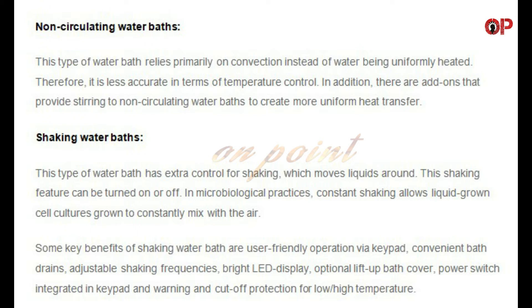Shaking water baths have extra control for shaking, which moves liquids around. This shaking feature can be turned on or off. In microbiological practices, constant shaking allows liquid-grown cell cultures to constantly mix with the air. Some key benefits of shaking water baths are user-friendly operation via keypad, convenient bath drains, adjustable shaking frequencies, bright LED display, optional lift-up bath cover, power switch integrated in keypad, and warning and cut-off protection for low or high temperature.